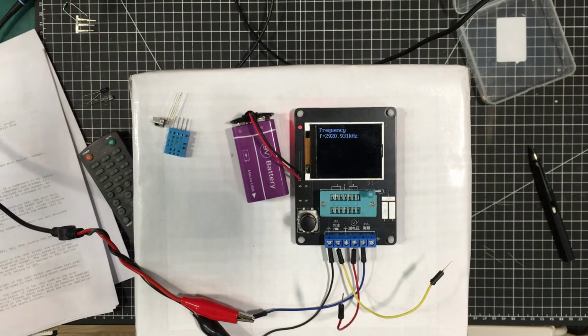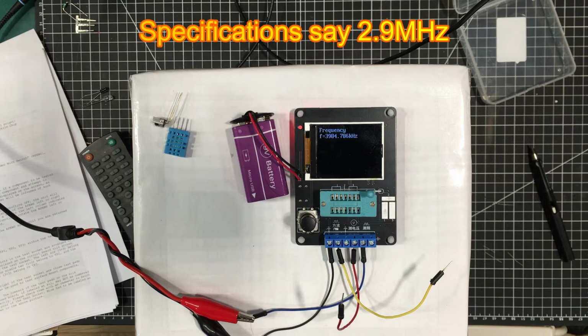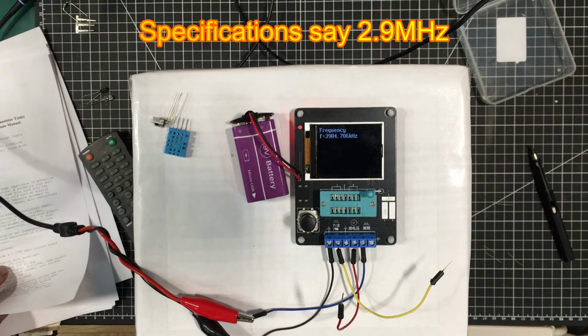Okay, let's try 3 megahertz. It says 2.920. What happens if we go up to 4? Okay, it seems to be able to measure 4 megahertz fairly reasonably. It's only off by about 16 kilohertz there. That's not too bad. Beats specifications on that, really.